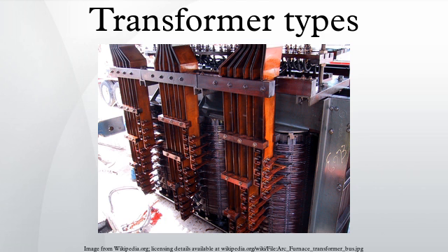These transformers simplify installation since they are dry, without cooling oil, and so require no fireproof vault for indoor installations. The epoxy protects the windings from dust and corrosive atmospheres. However, because the molds for casting the coils are only available in fixed sizes, the design of the transformers is less flexible, which may make them more costly if customized features are required.